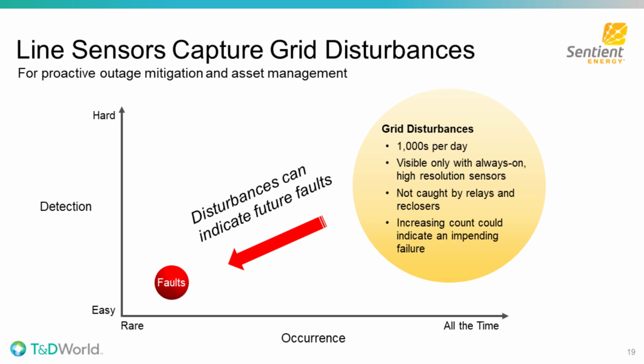If you're looking at your underground system out there for 40, 50 years, there are hundreds and thousands of sub-cycle events that happen every day in your cable system. But most of them don't get caught by typical relays and other IEDs that are looking for a 3-cycle, 3,000 amp fault surge. What we can do with our UM3 plus UM1 solution is monitor for quarter-cycle blips that increase over time. So if there's an increasing trend of such blips happening over a period of time, it could be a leading indicator for an impending failure.